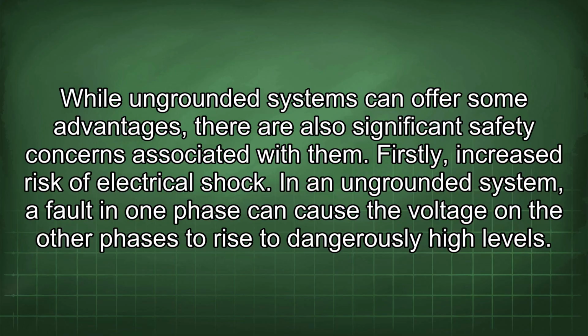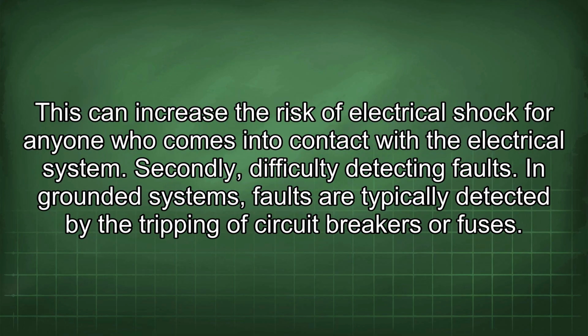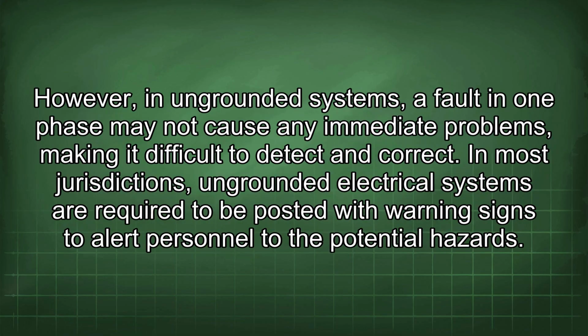In an ungrounded system, a fault in one phase can cause the voltage on the other phases to rise to dangerously high levels. This can increase the risk of electrical shock for anyone who comes into contact with the electrical system. Secondly, difficulty detecting faults. In grounded systems, faults are typically detected by the tripping of circuit breakers or fuses. However, in ungrounded systems, a fault in one phase may not cause any immediate problems, making it difficult to detect and correct.